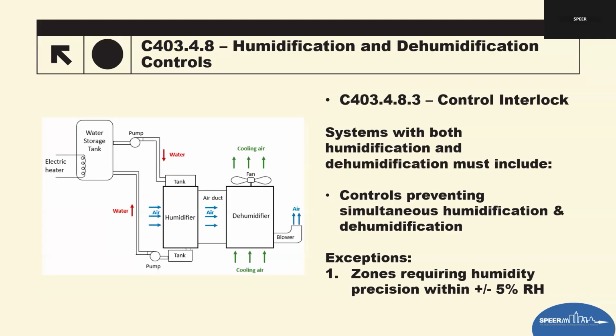Plan review tips. So look for humidity set points and deadband values in the controls narrative. Confirm equipment cannot exceed humidity thresholds. And then verify there's an interlock logic between humidification and dehumidification, unless it meets that exception. Field inspection. Check controls trend log for simultaneous heating and humidification and dehumidification. So if it's been running, show me the logs. Make sure it has not run at the same time. Verify actual relative humidity limits in the building's automation system. That's the BAS. And then confirm the exceptions, if they're using them, are justified and clearly documented.